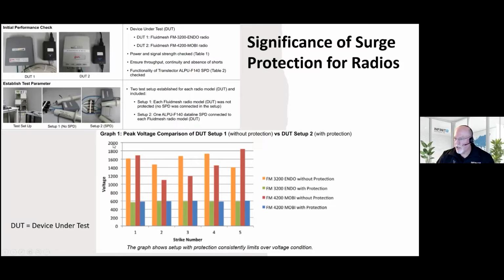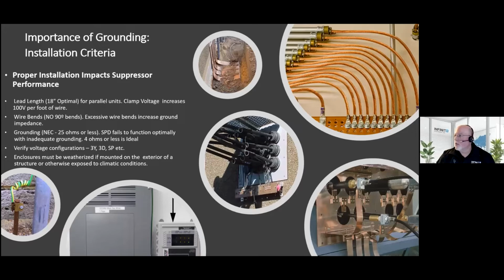So you can see voltage here. This is how much voltage got to the equipment during the test. And all of these taller lines are the unprotected radio. And for the protected radio, the voltage was limited to below 600 volts. So surge protection works. Very critical to surge protection is grounding. So that's really foundational. If that isn't done correctly, then it's kind of a moot point.